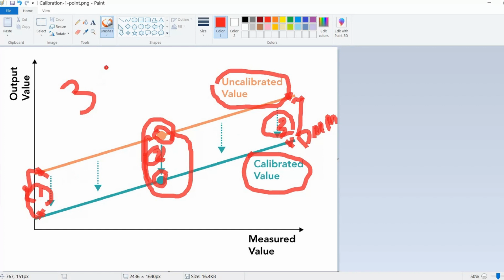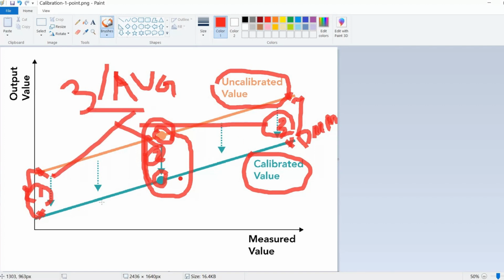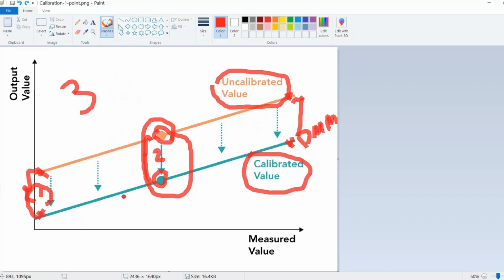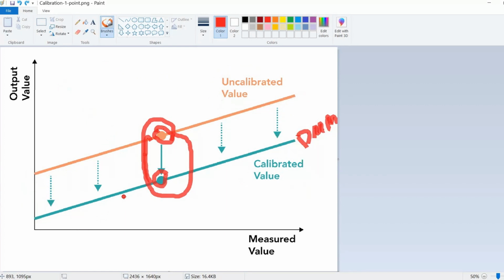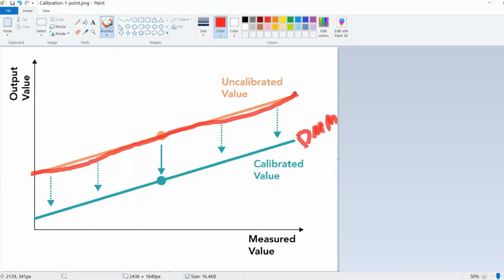So for these three points, I will take the average, AVG, of these three points. Then I will use this single value, the average of these three points, in my equation. This is how it works for single point calibration. Again, the raw data that we measure is in the same slope as the actual, correct data.